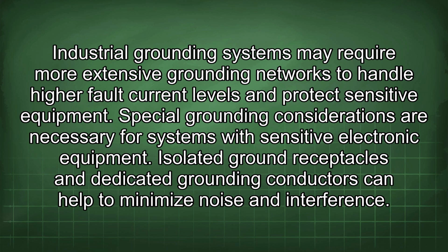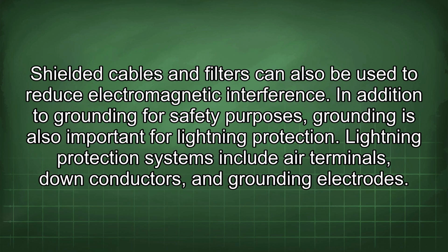Special grounding considerations are necessary for systems with sensitive electronic equipment. Isolated ground receptacles and dedicated grounding conductors can help to minimize noise and interference. Shielded cables and filters can also be used to reduce electromagnetic interference.